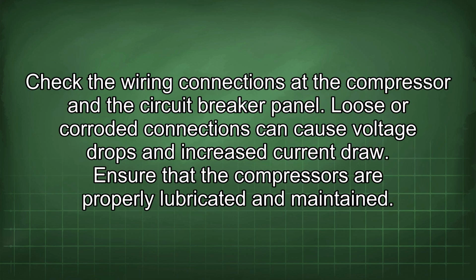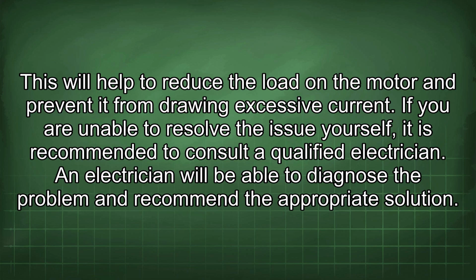Check the wiring connections at the compressor and the circuit breaker panel. Loose or corroded connections can cause voltage drops and increased current draw. Ensure that the compressors are properly lubricated and maintained. This will help to reduce the load on the motor and prevent it from drawing excessive current. If you are unable to resolve the issue yourself, it is recommended to consult a qualified electrician. An electrician will be able to diagnose the problem and recommend the appropriate solution.